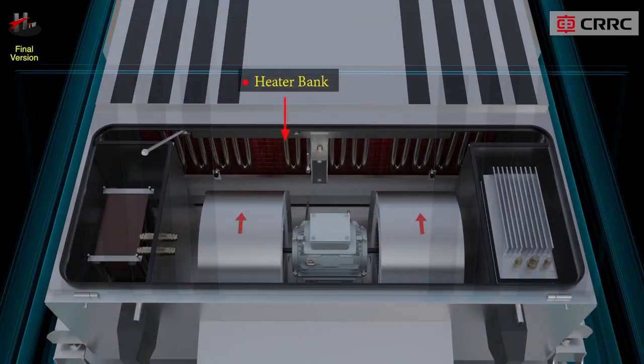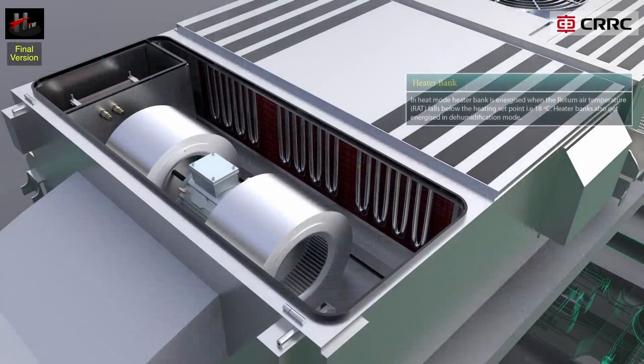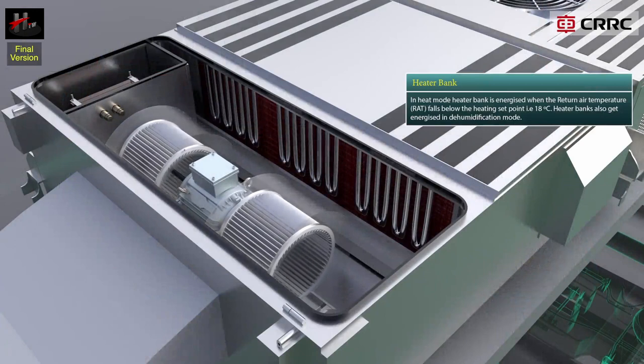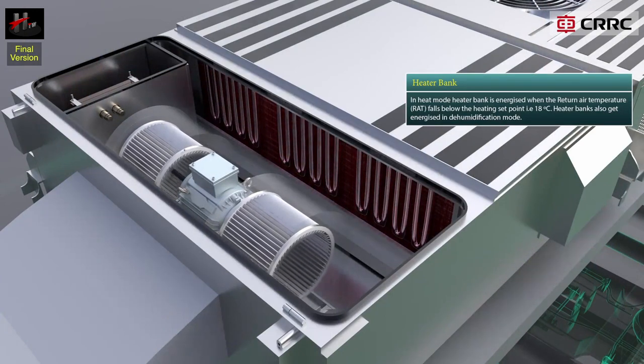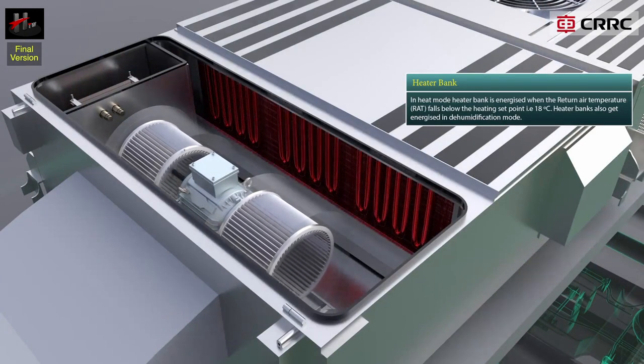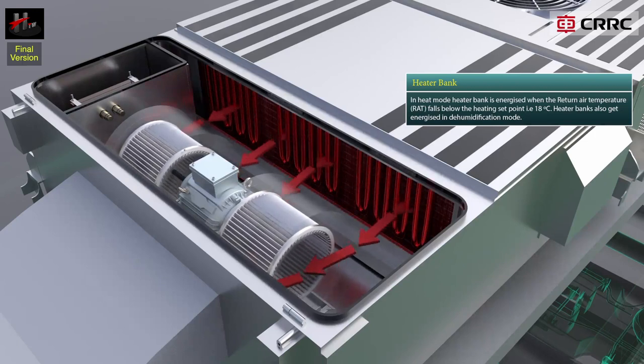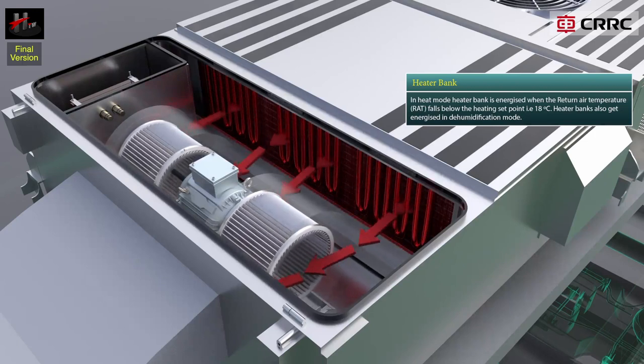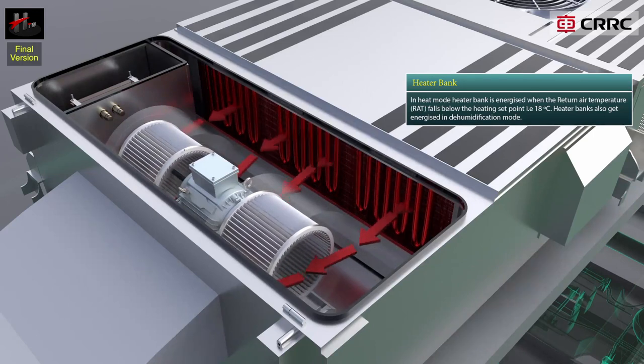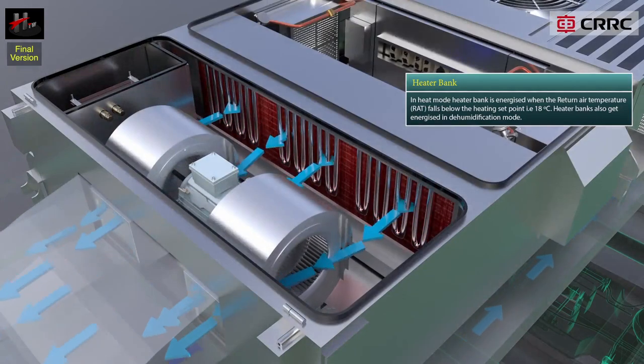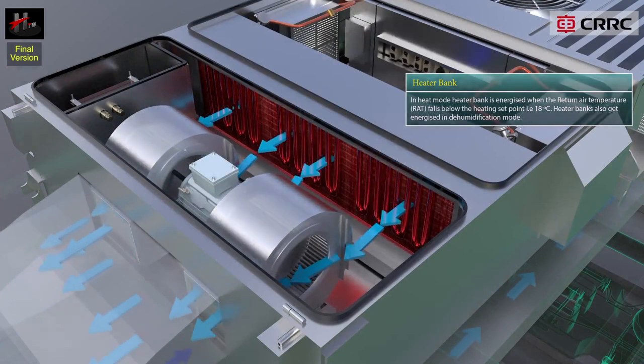The heater bank is installed on the downstream side of the cooling coil. In heat mode, the heater bank is energized when the return air temperature or RAT falls below the heating set point of 18 degrees centigrade. The heater bank also gets energized in the dehumidification mode.